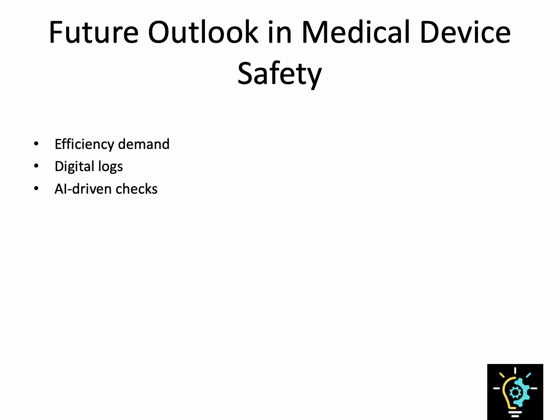What is the future outlook in medical device safety? Looking ahead, IEC 62353 is likely to evolve alongside healthcare technology. One clear trend is efficiency. Hospitals and service providers want faster testing without sacrificing accuracy. That means more analyzers will integrate automated IEC 62353 routines. What this will do is sync directly to the asset management system you're using, and this can reduce paperwork and human error.